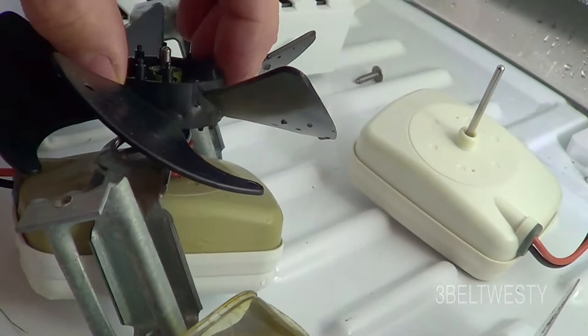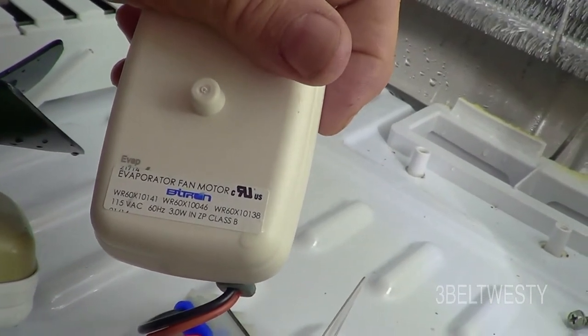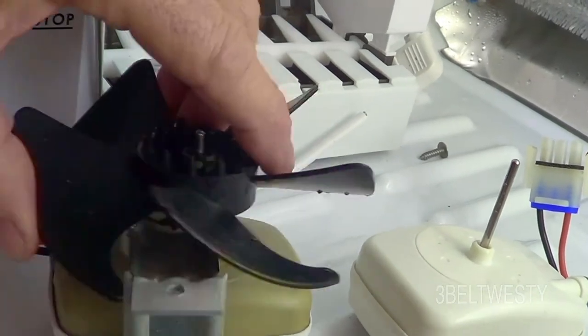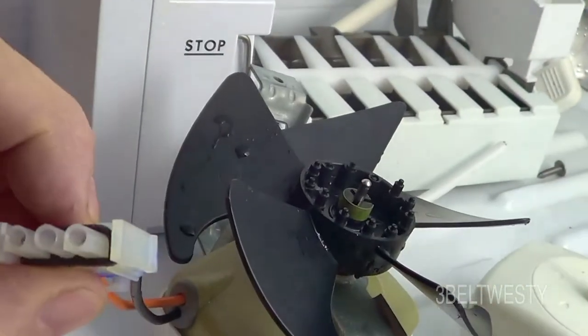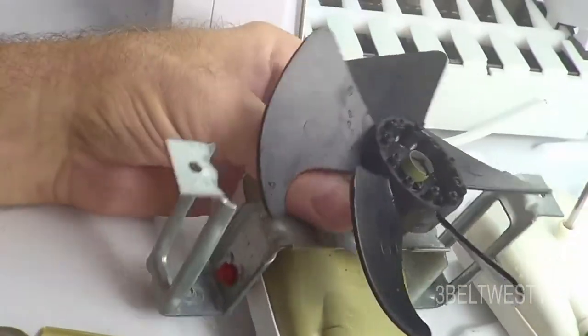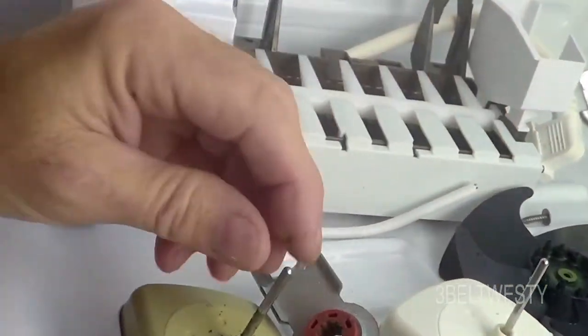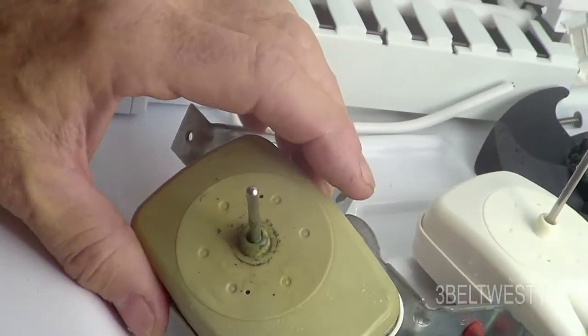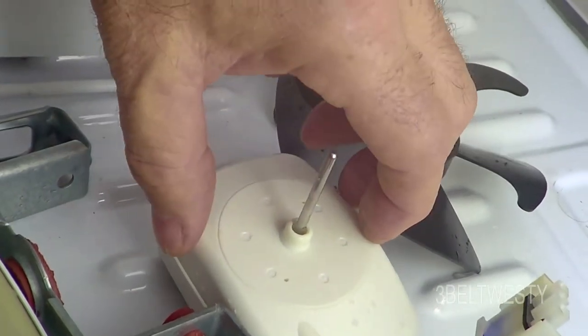It looks like the bearing is shot in here. It's a wobble around where the new one won't. Evaporator fan motor. That's a WR60X10046. So this one's fairly tight. This one's got a lot of loose as a goose bearing shot on it. Get the same connector. To get the fan off, it'll pull off with my fingers here. It's got just a friction fit. Pull the motor off. You can see the play on here. Still running, but it's just getting to be where it's kind of flopping around in the wind. It makes a lot of noise.